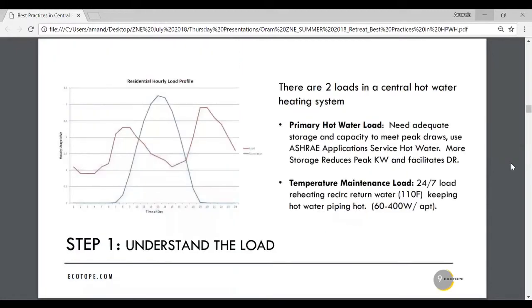So the first piece of this entire equation: you've got a big multifamily building, where do you start? Next slide, thank you. Step 1 is really understanding the load. Right now in a multifamily building, there are really 2 loads: the primary hot water load, and what we call the temperature maintenance load, which is keeping the water hot in the pipes. You have to respect both, because if you don't, they will mess things up, and I'll tell you some examples of how.